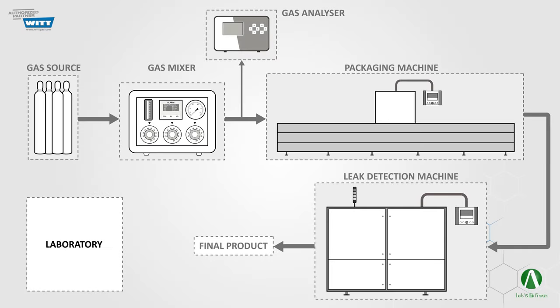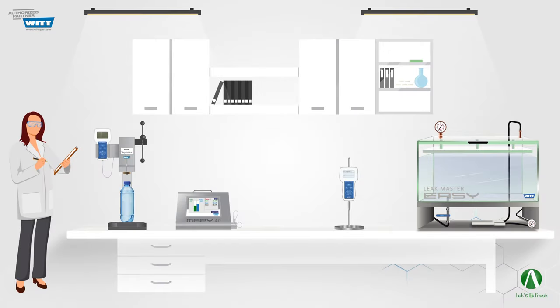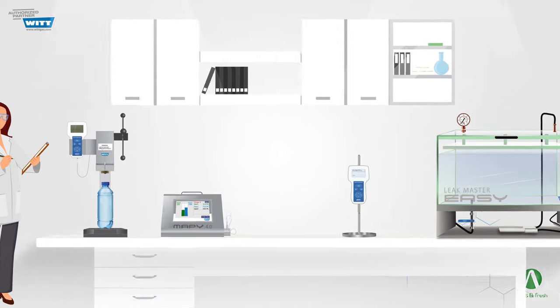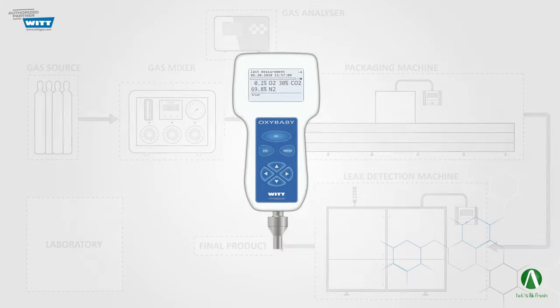In addition to the mentioned inline equipment, laboratory testing devices are used as well. In this case, quality control will perform some tests on randomly chosen packages to make sure about quality and market acceptance. Along with some other accessories, tabletop or portable gas analyzers can be used for analyzing the gas concentration inside different kinds of packages. Portable analyzers are highly applicable and very easy to use — they can be used for analyzing gas within the laboratory or directly on the production line.